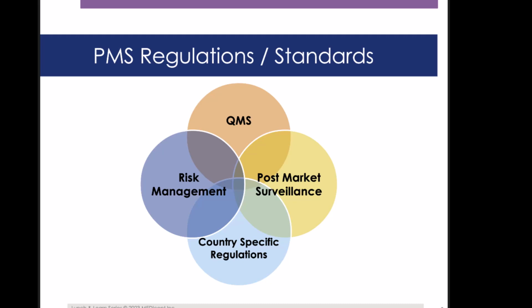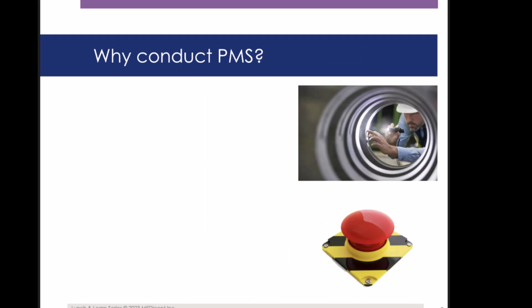Beyond the QMS and risk management requirements, there are post-market surveillance regulations that are dependent on the risks associated with the device and the country the device will be marketed. Recently, regulators have seen the value of real-world evidence and have put an emphasis on this data. This was seen in Europe with the EU MDR implementing detailed post-market surveillance process and documentation requirements. It is no surprise that this will continue to be a trend for regulations in the future. We've established what post-market surveillance is, so now we've got to establish why it should be conducted.